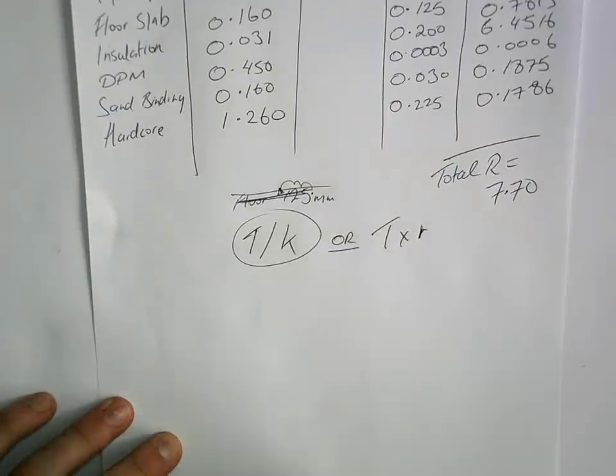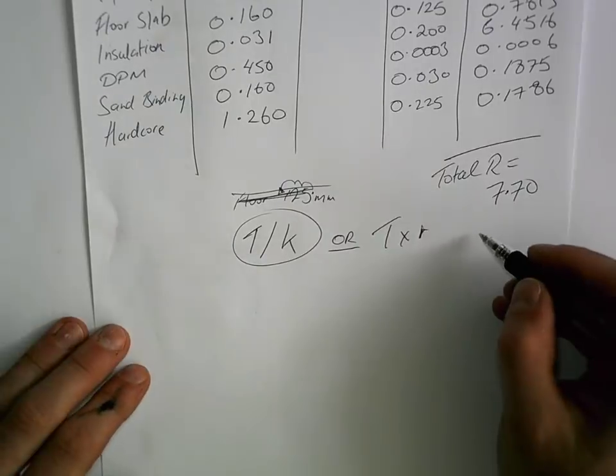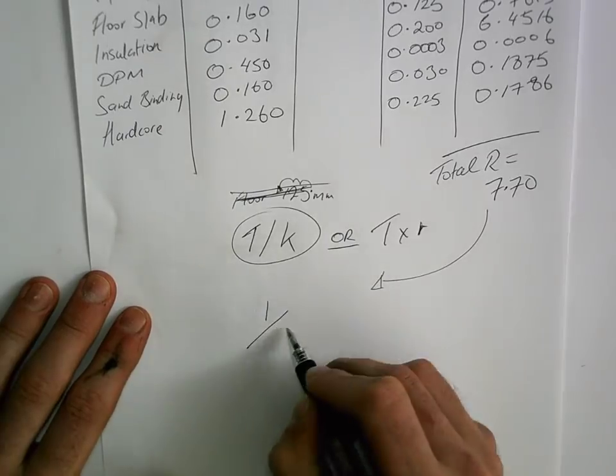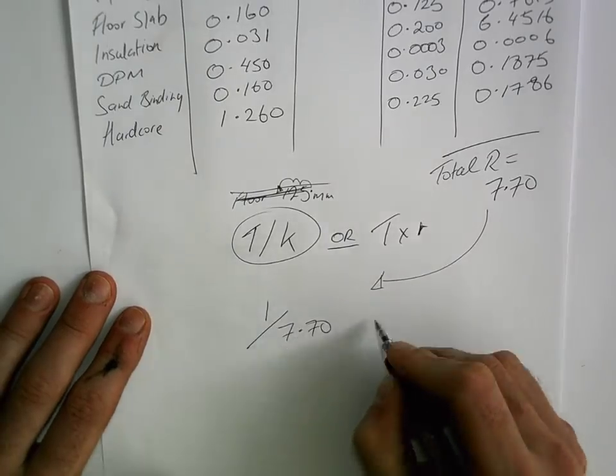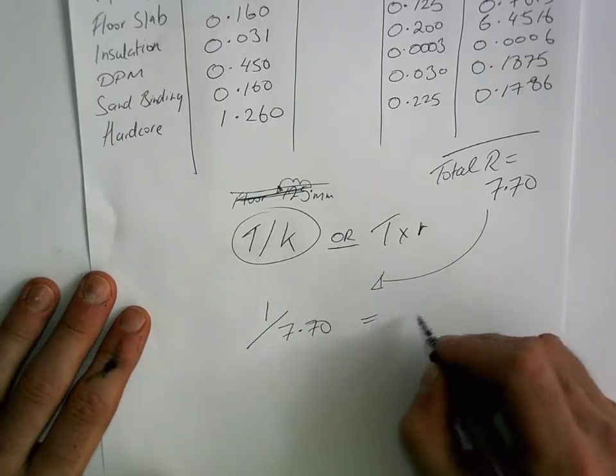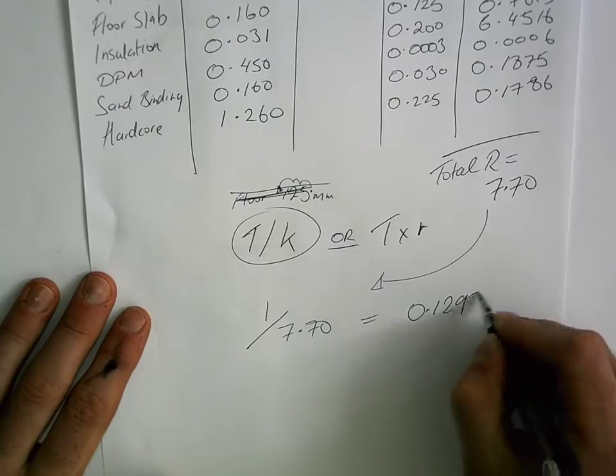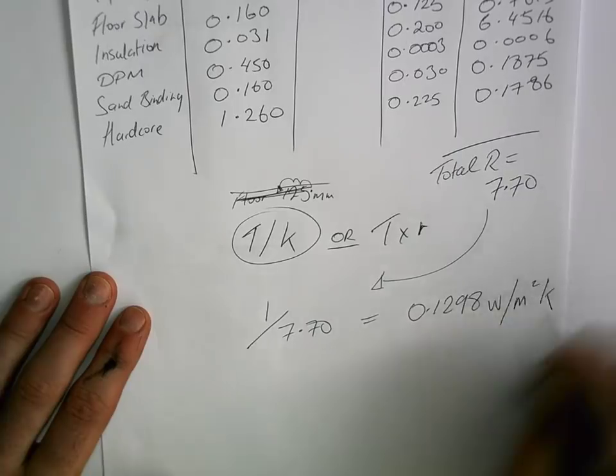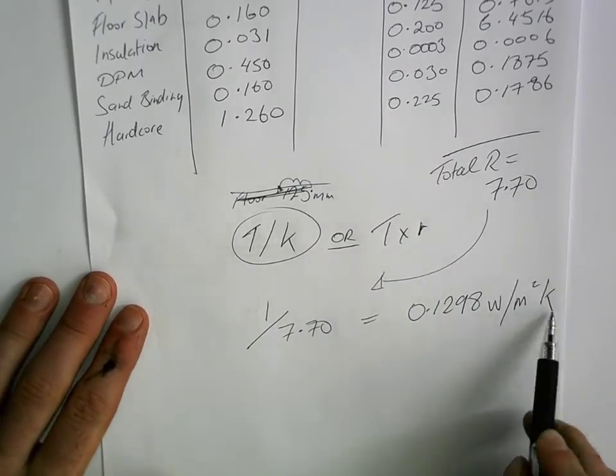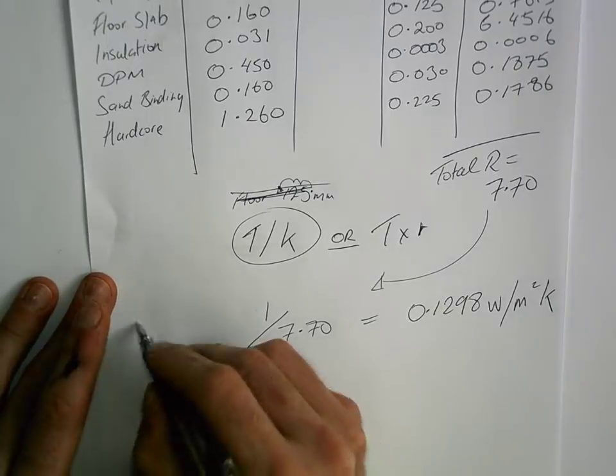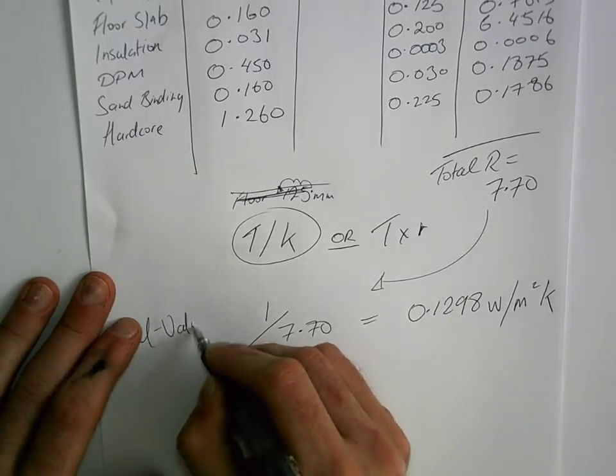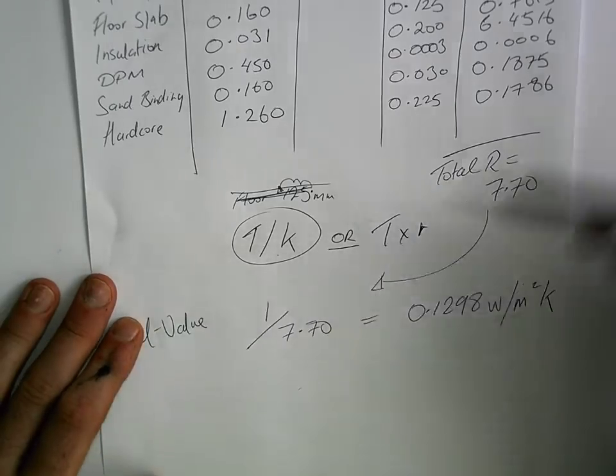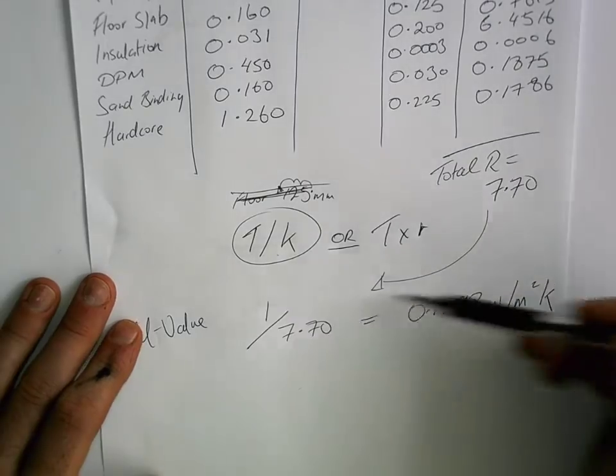The last stage of calculating your U-value is to take your total resistance and divide it into one. So that's 1 divided by 7.70, which gives a U-value of 0.1298 watts per meter squared degrees Kelvin. Make sure you include those units to get full marks. Learn those two formulas, total your resistances, divide into one — that's your answer.